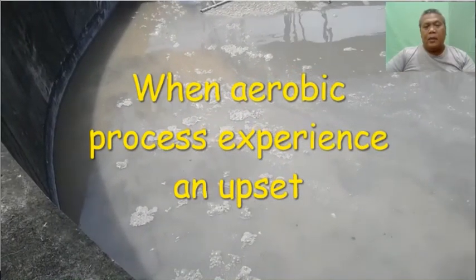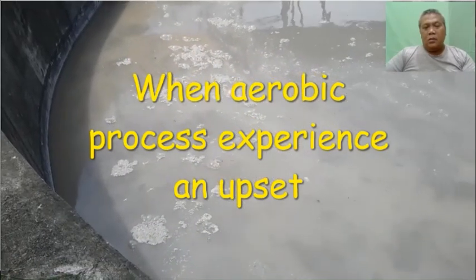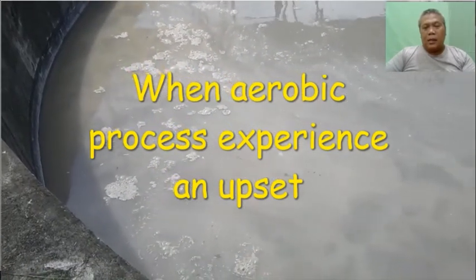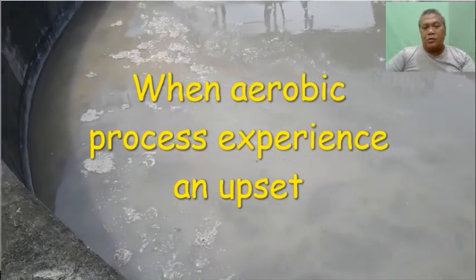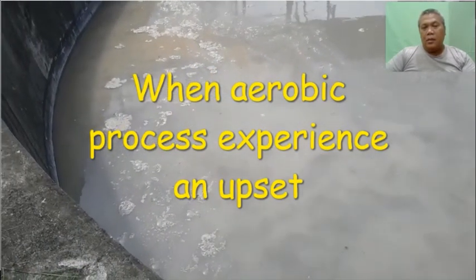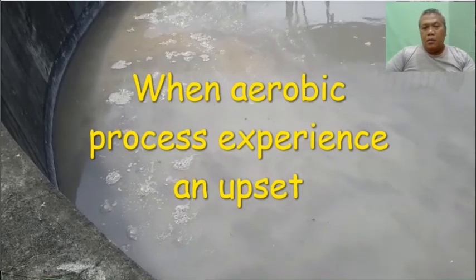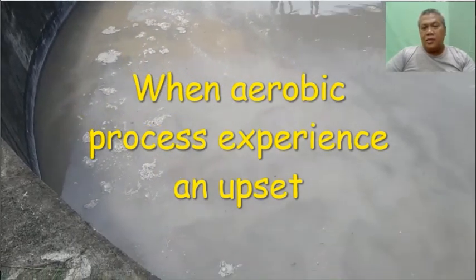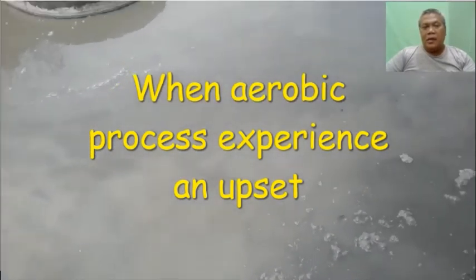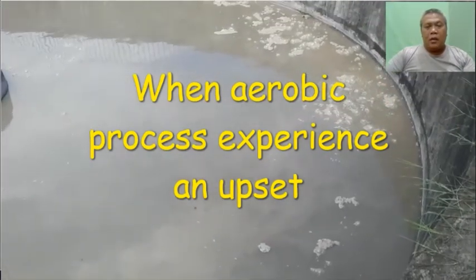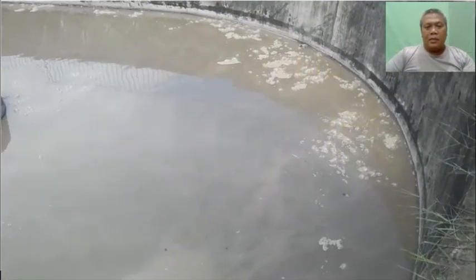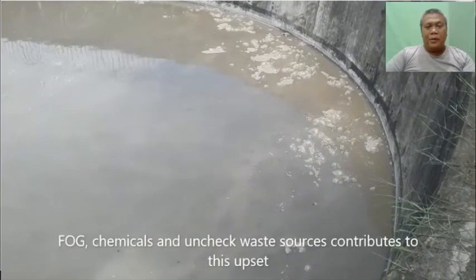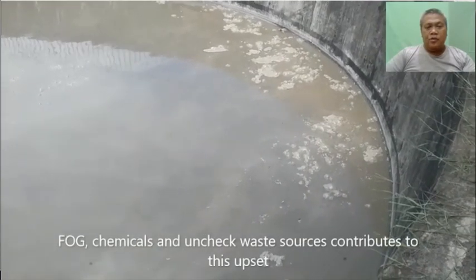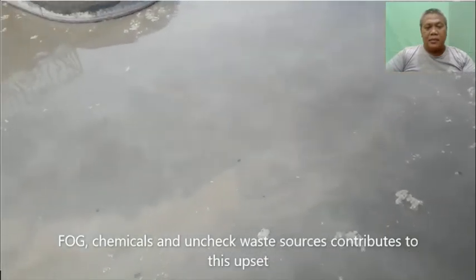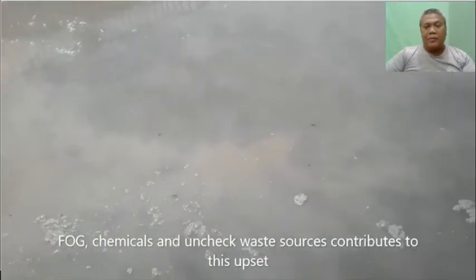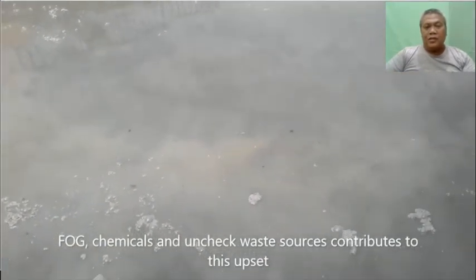However, when the aerobic process becomes upset or has an upset condition, then this will be the look of the oxidation ditch. So this is upset, no more treatment. In that case, we have to clean it up. And this is due to FOG, chemicals, and unchecked waste coming into the oxidation ditch.